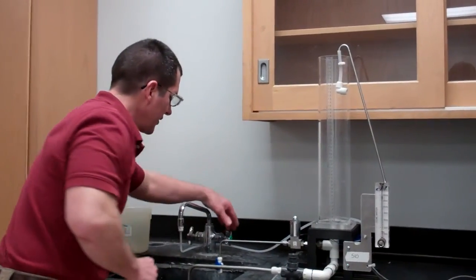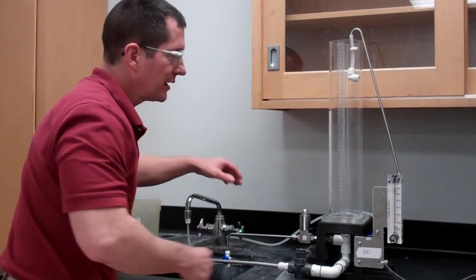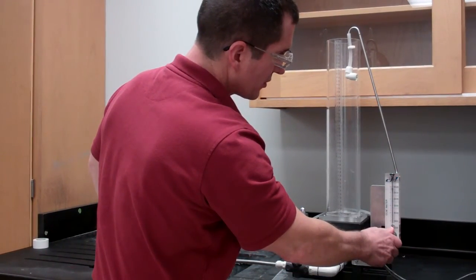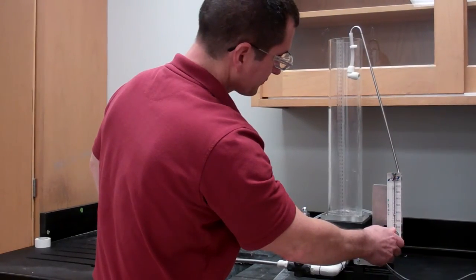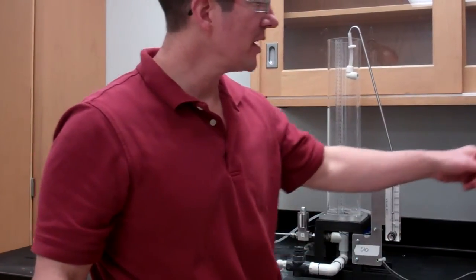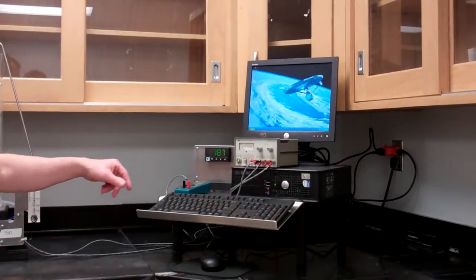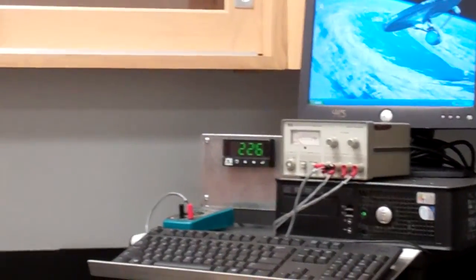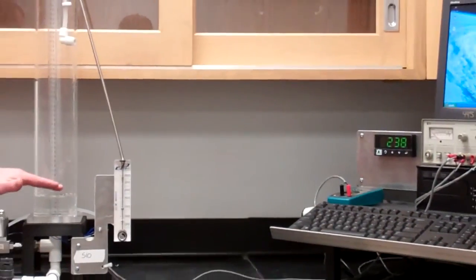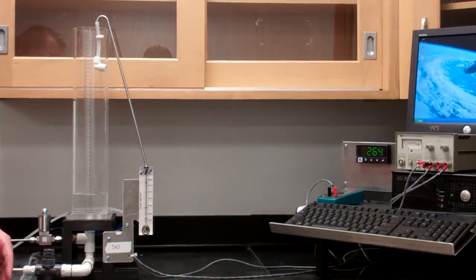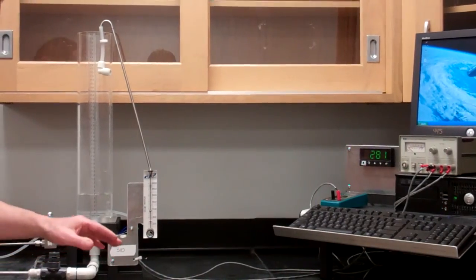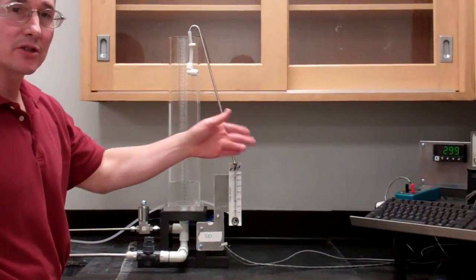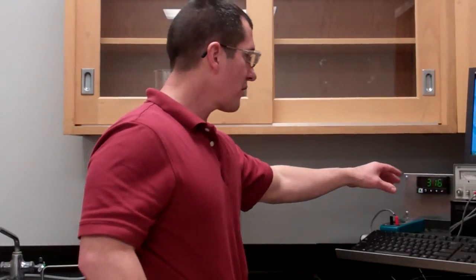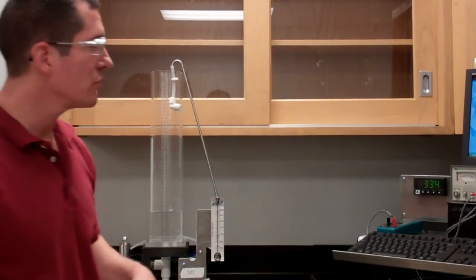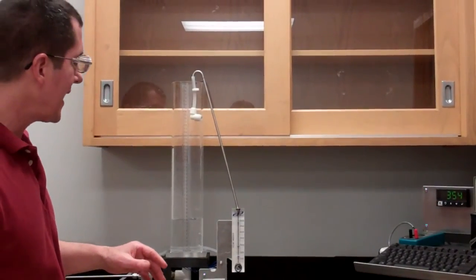And here's your water supply. Turn this on. It goes to this rotameter, so I can start putting some water in with the rotameter. And if you notice, right over here, this is a display for the differential pressure transducer signal. As the level of water in the tank rises, so does the output of the sensor. Now, remember, the measurement sensor output is the input to the controller. So this is our controller here, and right now it's just set to monitor only. It's not going to provide any output.